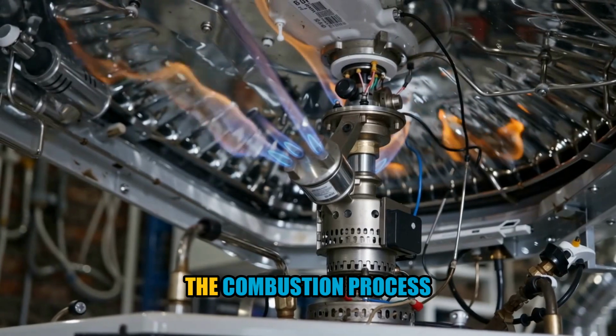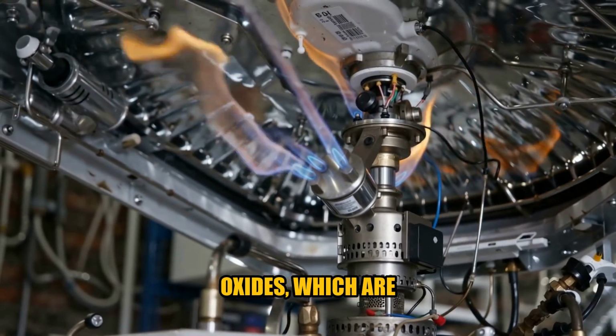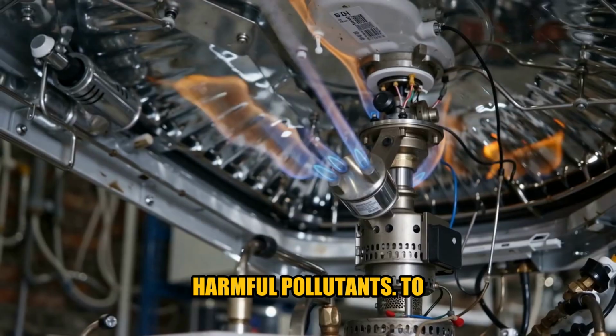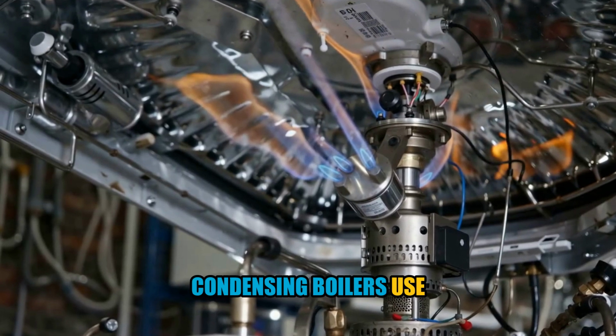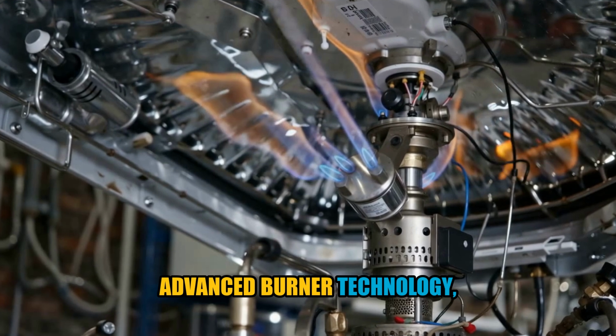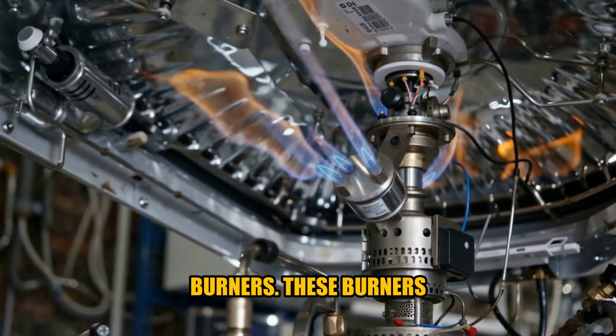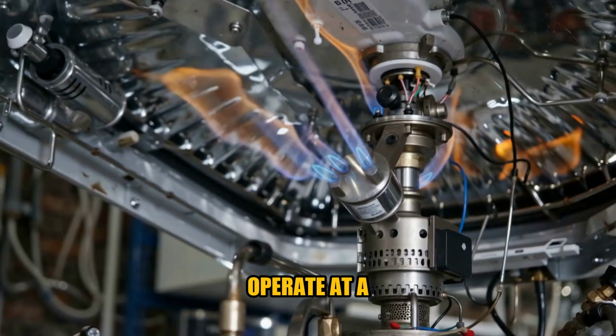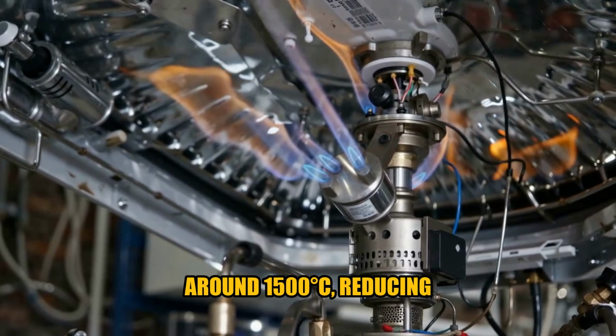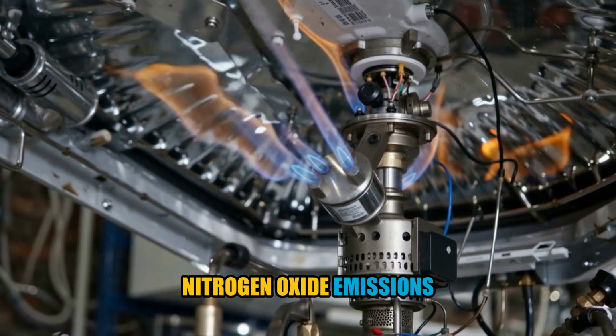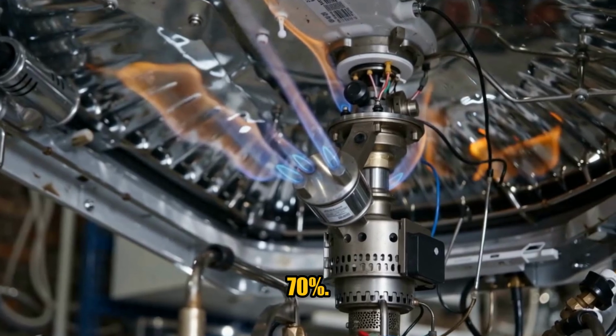The combustion process also produces nitrogen oxides, which are harmful pollutants. To reduce these emissions, condensing boilers use advanced burner technology, such as low NOx burners. These burners operate at a lower temperature, typically around 1500 C, reducing nitrogen oxide emissions by up to 70%.